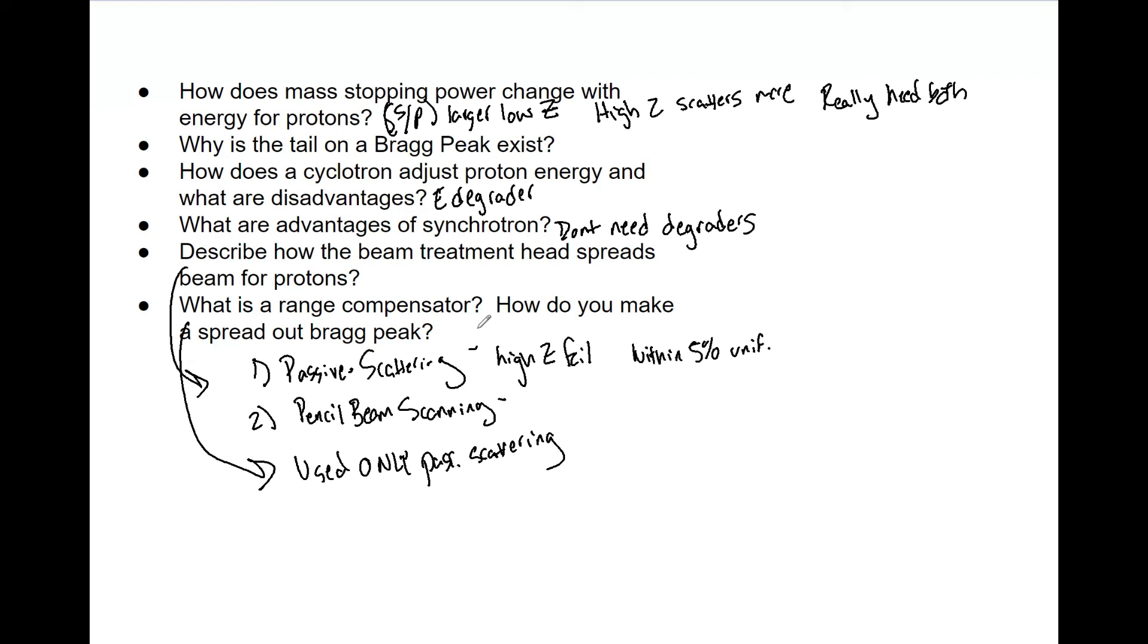Now, how do we make a spread out Bragg peak? You want to use a range modulator, which is a wheel with different thicknesses of layers of plastic to spread out that Bragg peak. I know there are a lot of terms, and that's why I made a lot of note cards and drove this home. Without working in a proton clinic, it was difficult for me to understand range compensator, range modulator, passive scattering, pencil beam scanning—there are so many terms. Protons can seem like their own world.